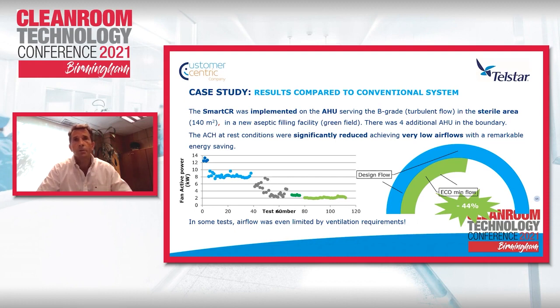Very briefly, the conclusion is that the eco minimum flow, with all the safeties taken, could be reduced easily by 44%. We could reduce it much more than that, but with safety considerations and agreement with the client, we set it at a 44% reduction relative to the conventional scenario, and no less. Here in this diagram on the left, you can see different points regarding different tests we made at different velocities, fan velocities.